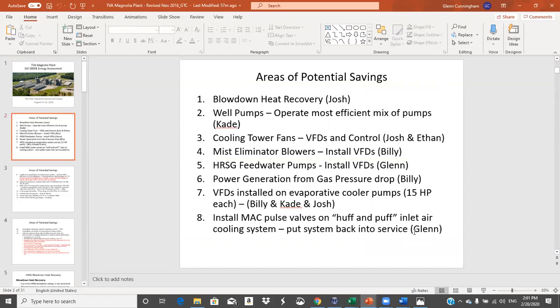And you say, well, how does that save energy? Well, the cooling tower fan will follow the fan affinity laws pretty well. And the fan affinity laws say that, for a cooling tower, fan flow is equal to capacity. So if I need 60% capacity, I need 60% fan flow. Way 1, 3 times 200 horsepower equals 600 horsepower. With the affinity laws, if I need 60% of this, I need 60% of this, and fan speed and capacity are 1 to 1.